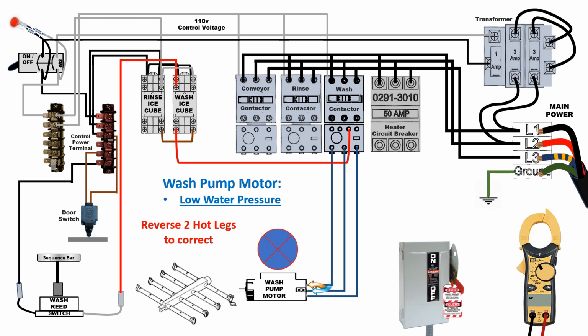Again, reversing any two of the hot legs that run in direct contact with the motor will reverse the polarity of the motor. If you have just finished replacing the motor and you've put the machine back together, reversing the polarity at the contactor will do the same job as at the motor.